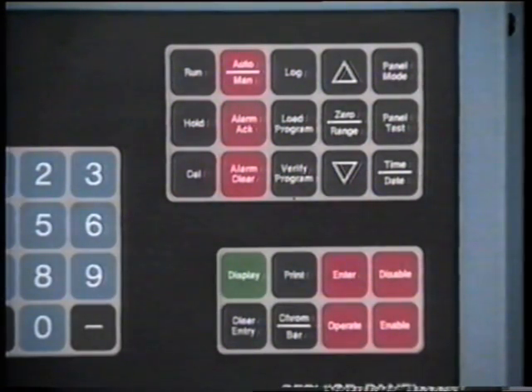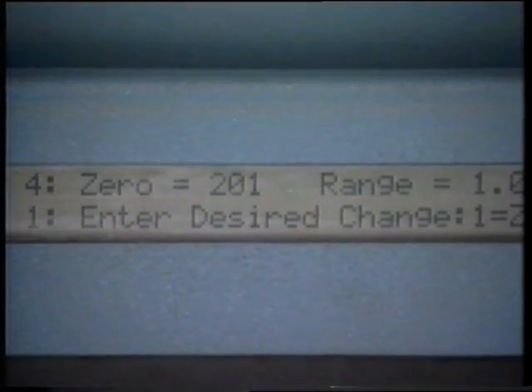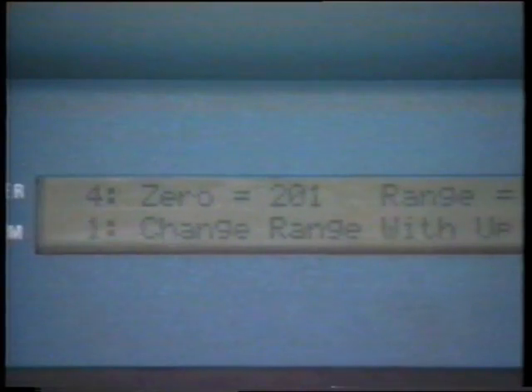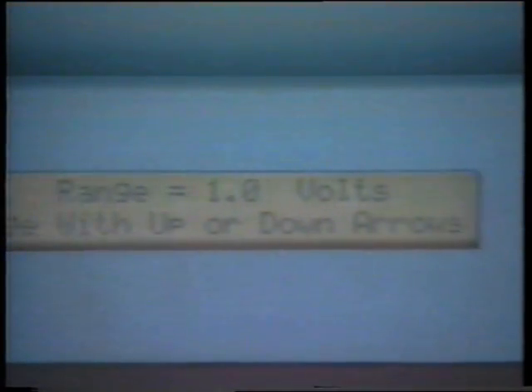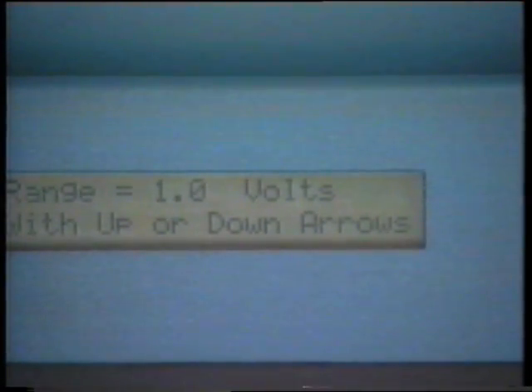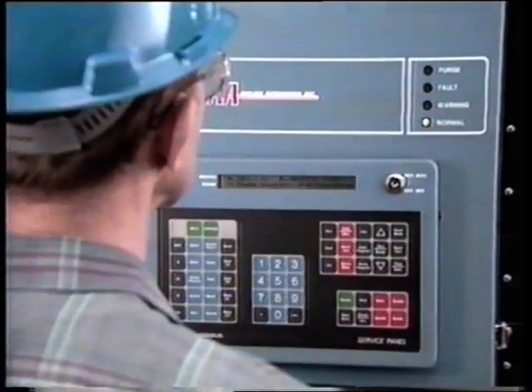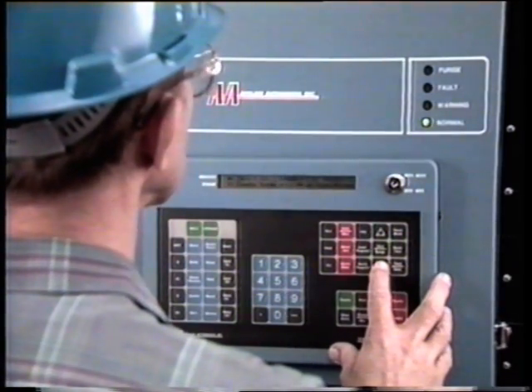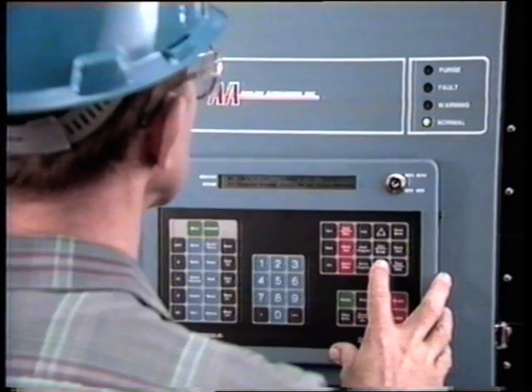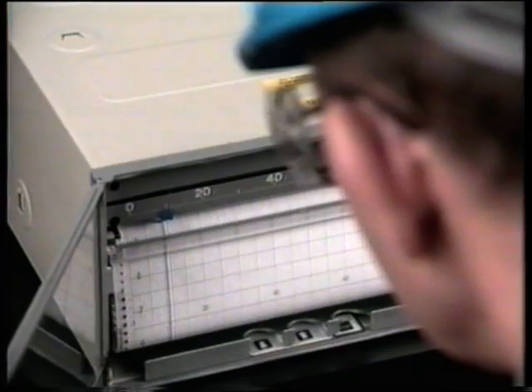Set the detector range to 0.2 volts as follows. Press 0, Range. The display will prompt you to select Desired Change in Detector Range. Press 2 and enter. The display will show the current range and prompt you to make adjustments by using the up and down arrows. Press the appropriate arrow until the display range equals 0.2 volts.